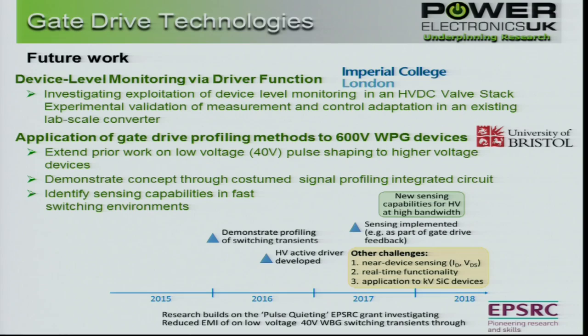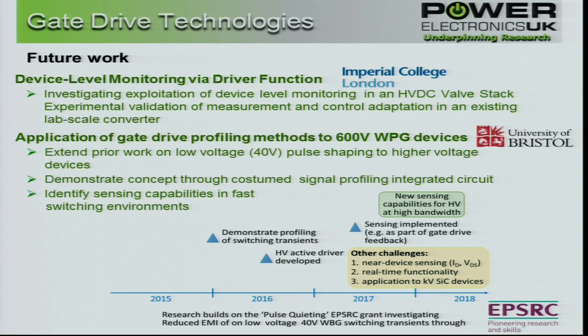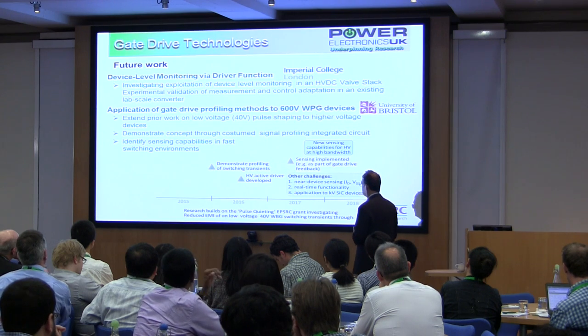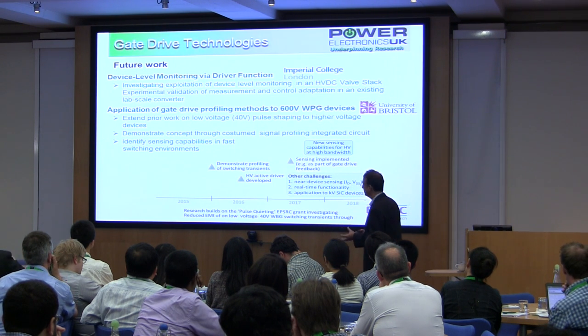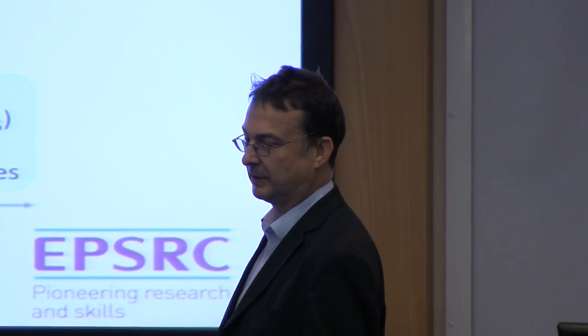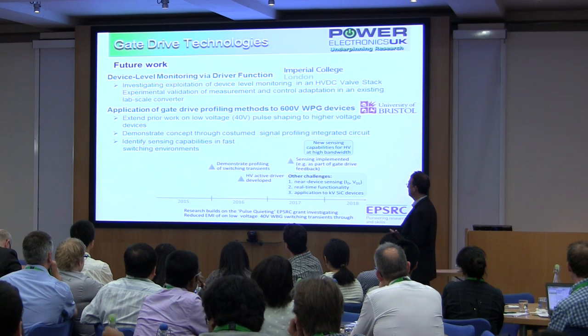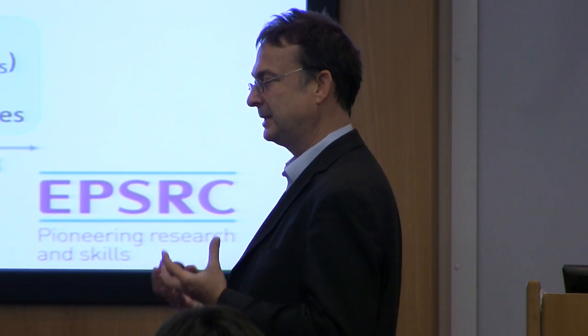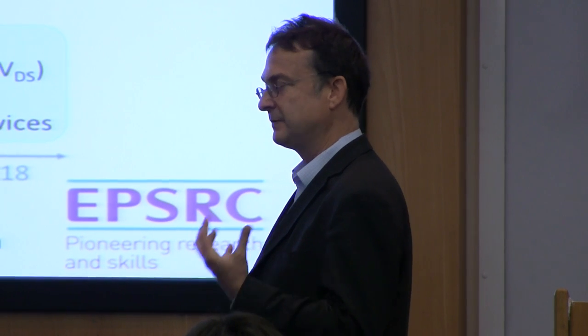In terms of future work: device-level monitoring via driver function — we're going to take that concept to our high-voltage DC valve stack and look at what we can measure, with experimental validation of measurement and control adaptation in a lab-scale converter. We're also looking at gate profiling activities, taking previous EPSRC-funded work that led to a custom integrated circuit capable of profiling gate drive waveforms — demonstrated on a 40-volt system — and scaling that to a 600-volt or higher system.